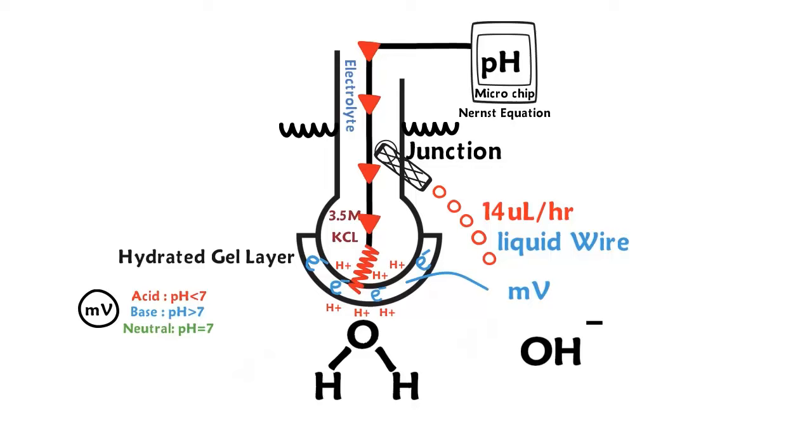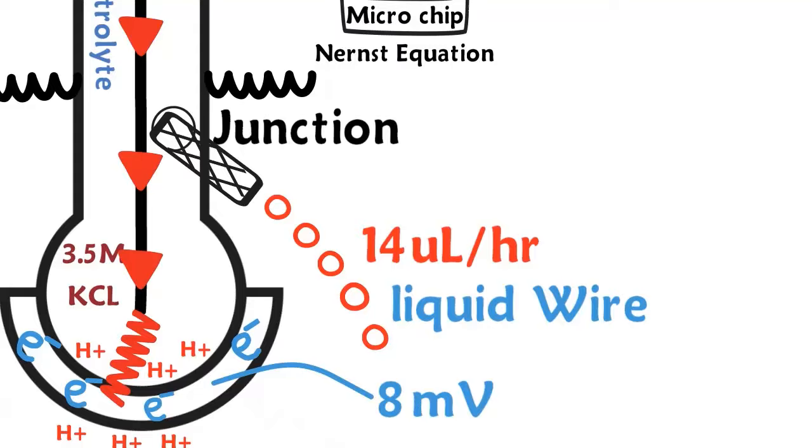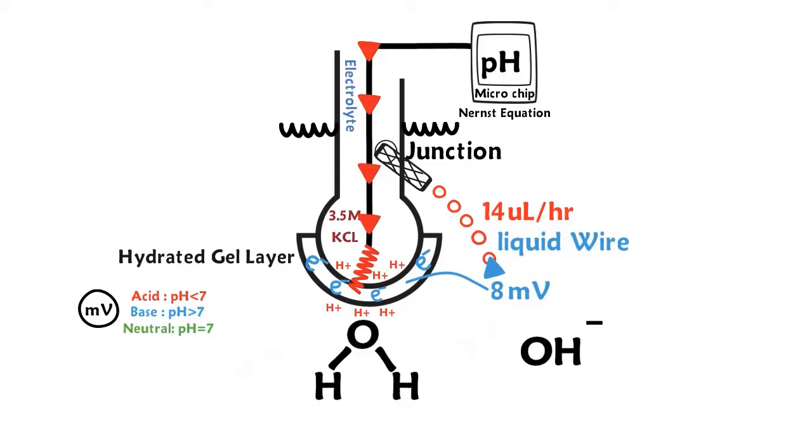This 8 millivolt charge needs to re-enter the pH electrode to be transmitted to the microchip so the Nernst equation can provide a pH value. The junction type leaking 3.5 molar KCl, a high salt electrical conductive solution into your sample, will now serve as a liquid wire to transmit the 8 millivolt signal through the liquid wire, junction, metal wire, and into the microchip so the Nernst equation can generate a pH value.